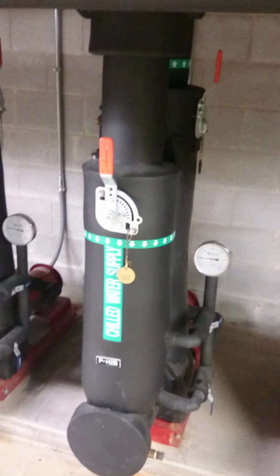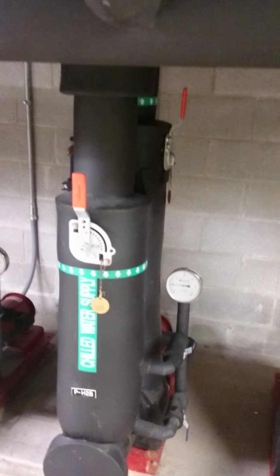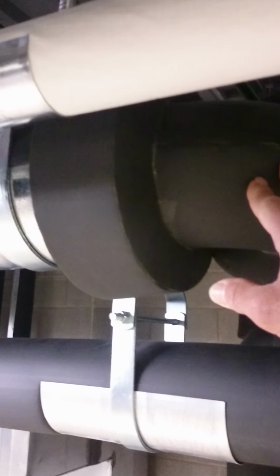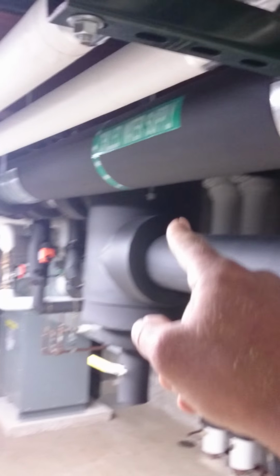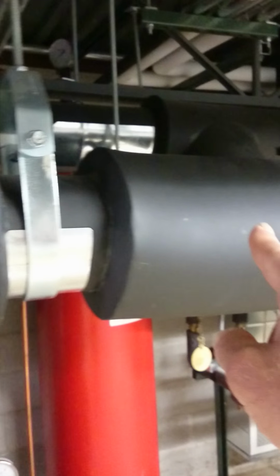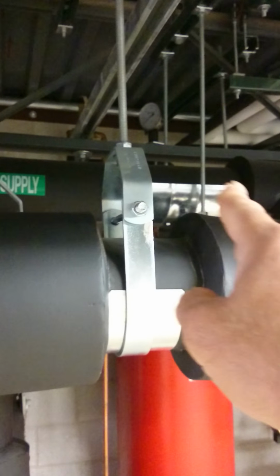So we've got 3 pumps here. These 2 pumps here are lead lag operated, so only one of these pumps needs to run at a time. And these are our main loop pumps. So this here would be our supply, so the discharge from the pump, and that's going to head around the building to numerous air handlers. And then we loop back on the return. Here's our air separator. We come back on the return line. And this pipe here heads to the return to the pumps.